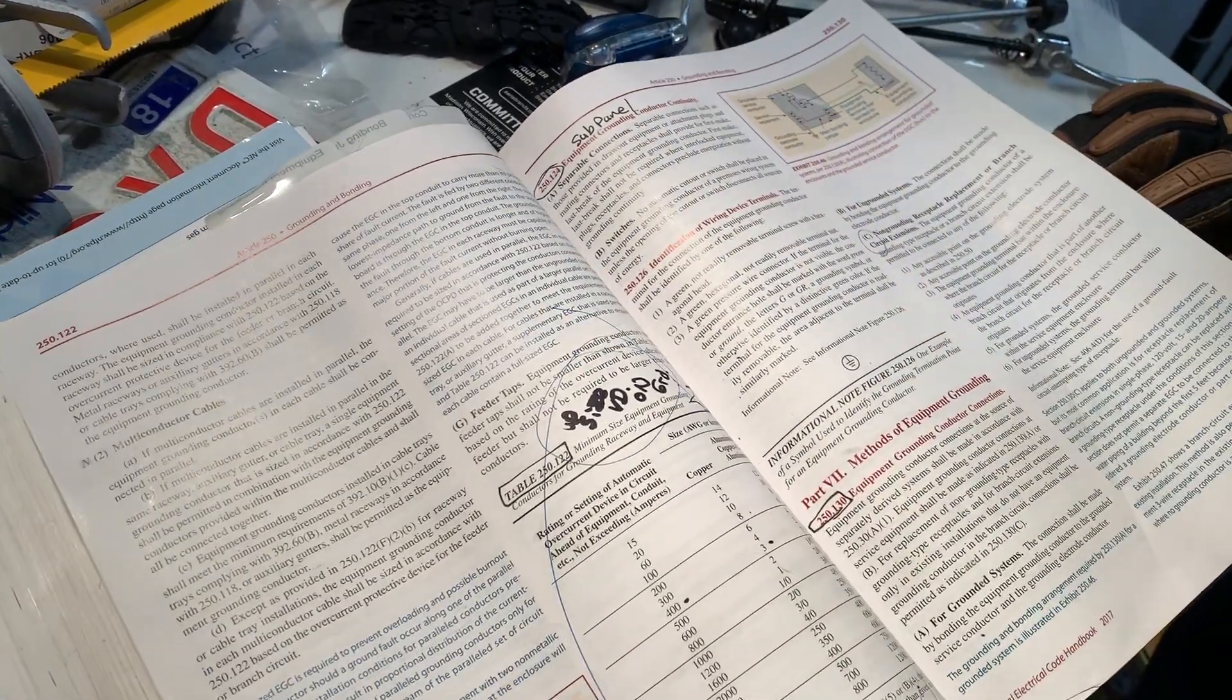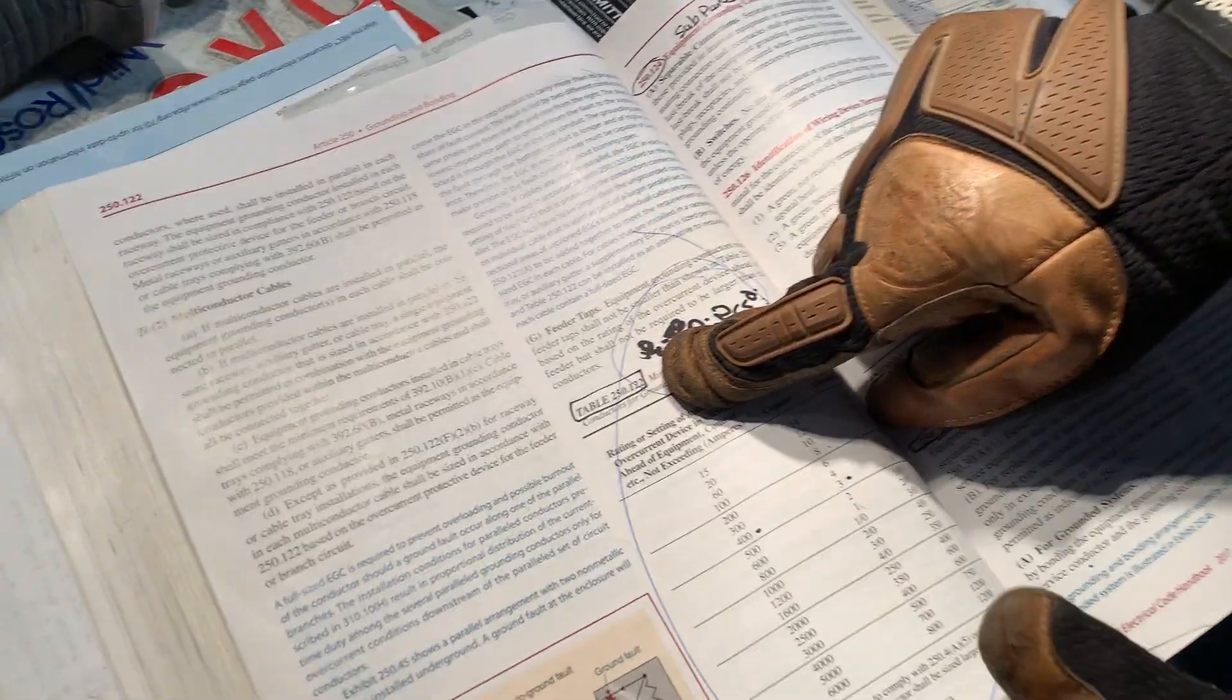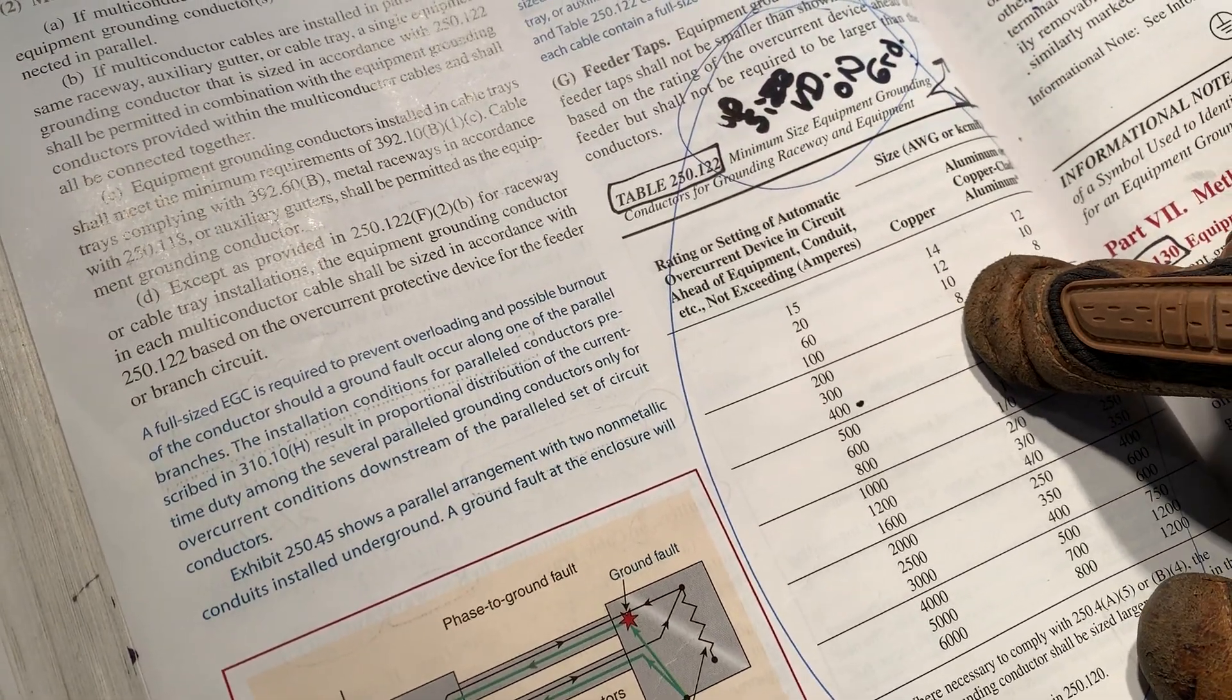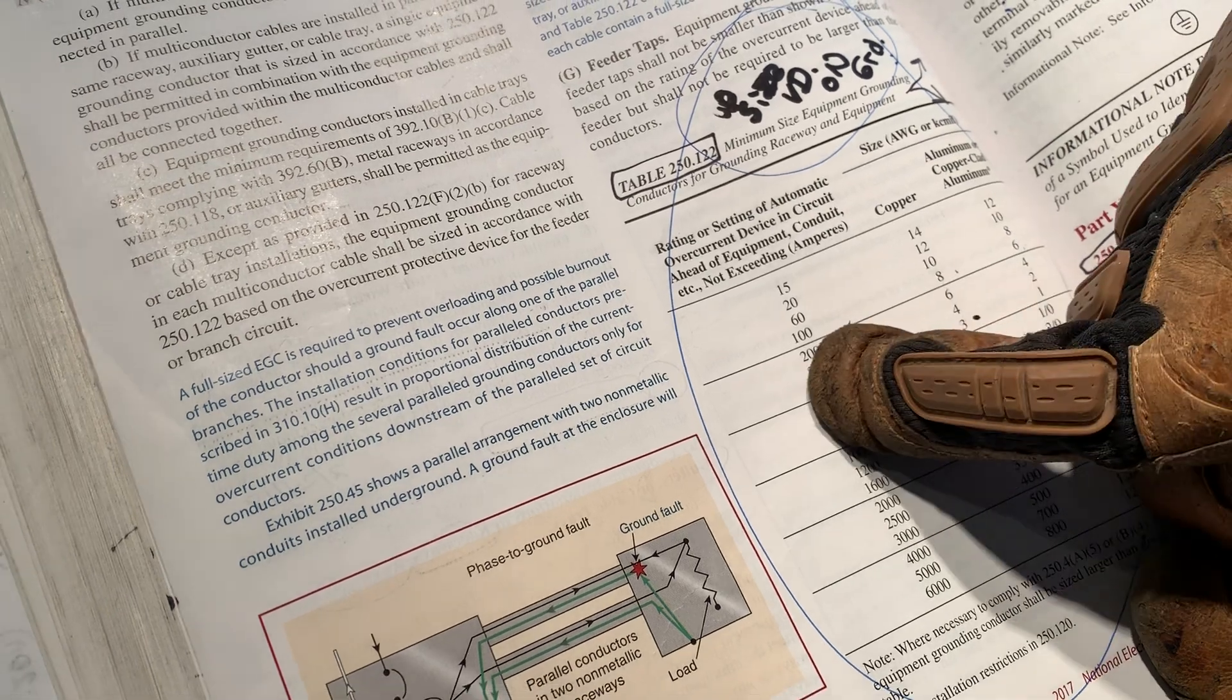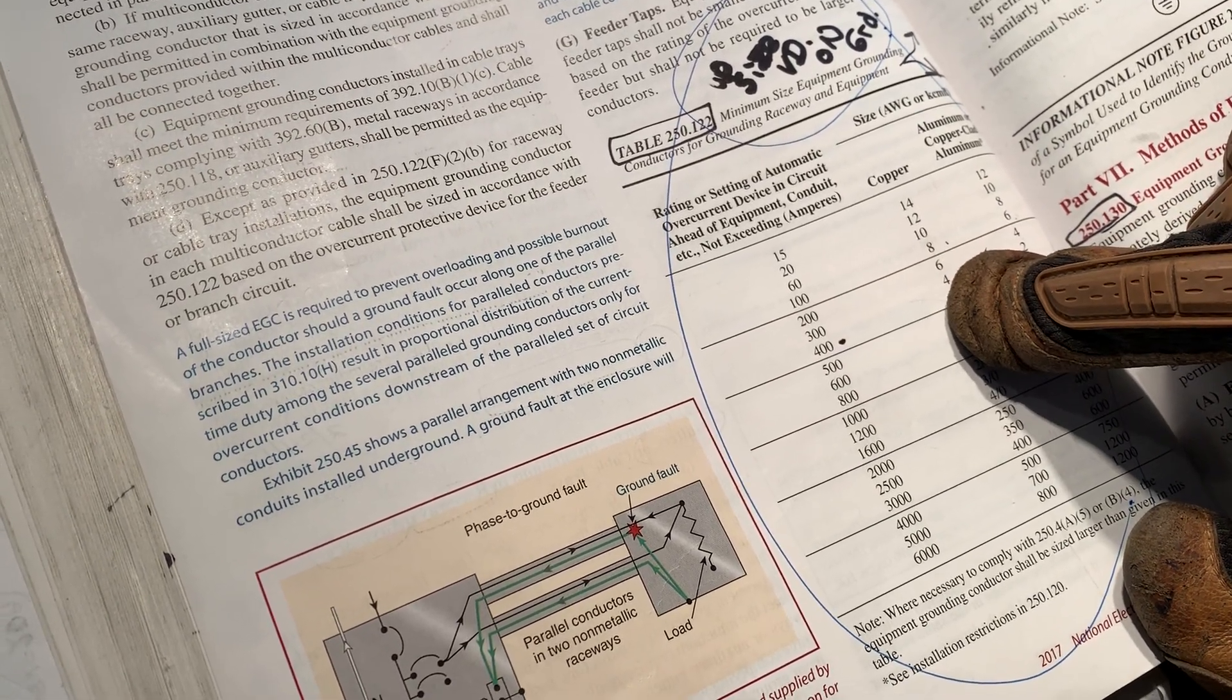Another common mistake I saw about this wiring installation: grounding. 250.122, he was feeding a panel at 60 amps. He needed a number 10. He has 6. That's good. I upped it to 100 amp. I had to have a number 8 gauge copper. I put in a 6, so I put in a 6. So I'm good there.